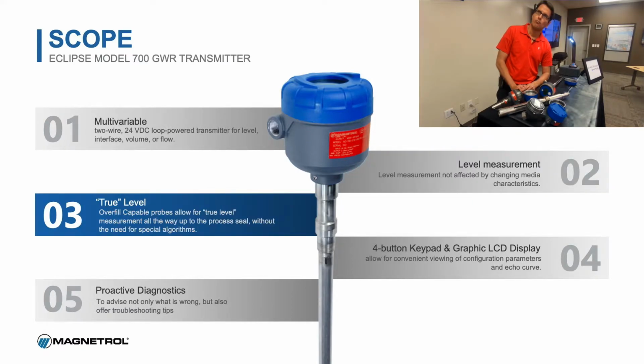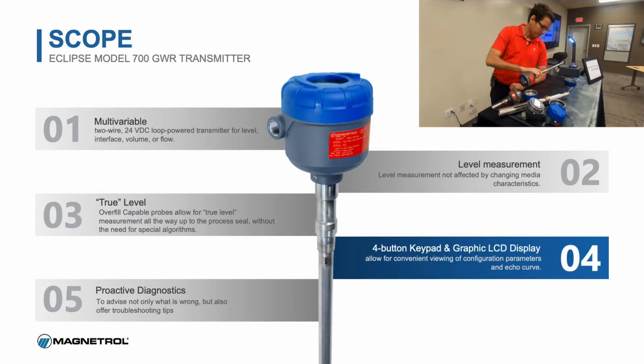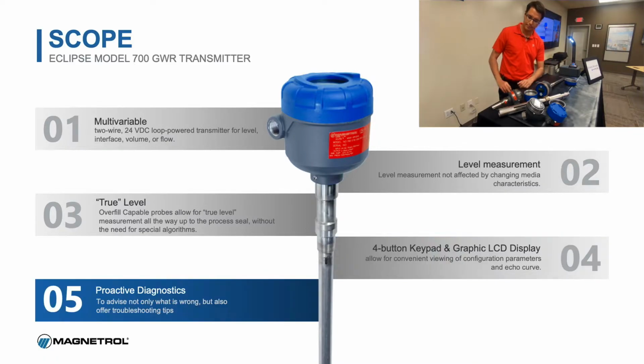And this true level is overfill capable. With that coaxial probe that you see pictured right there, that basically means that you can measure right up to the top of the probe, right up to the thread engagement, all the way up to the seal. We have the 4-button keypad and a graphical LCD display. The display is so good that you can actually see the echo curve the same way you could if you were using it with HART and a computer. And I will also say to you that if you know the 706 configuration hierarchy, you will absolutely know the 700 because they're the same exact menu tree.